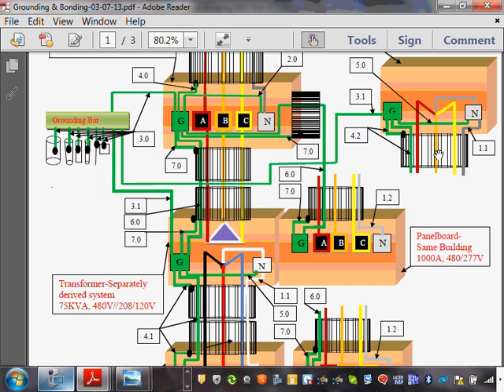Done, right? We lost the service. We're running on generators only. Where would the neutral current go? It's going to go back to the source. If you don't bring the neutral, the only way the neutral current is going to go back to the source is through the grounding electrode conductor and the ground electrode system, which is not acceptable.